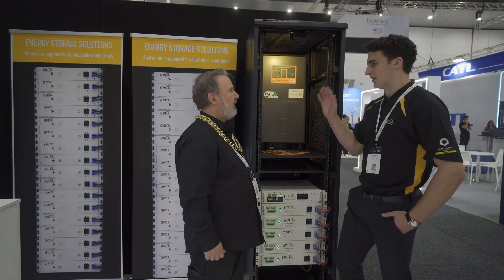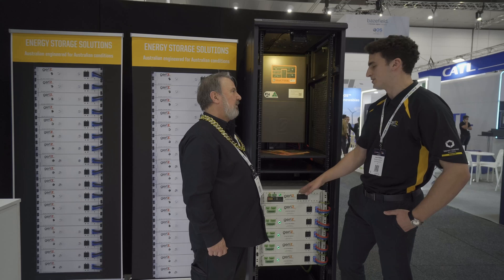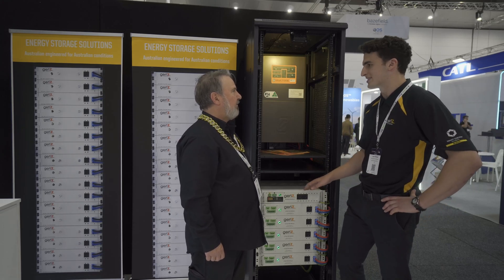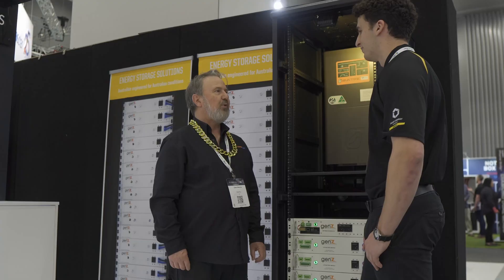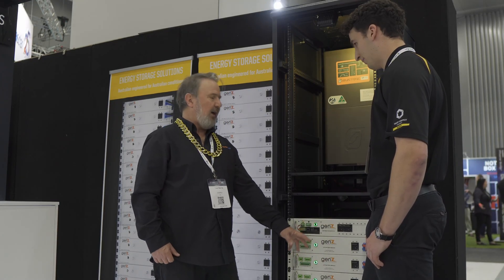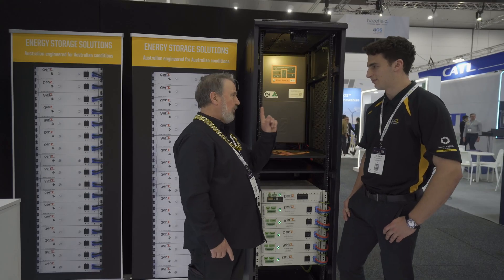This blank is basically for when you've filled up a rack and you want the full 250 amp output. You can then set up two sets of breakers in parallel, which gives you proper management of your fault currents and allows you to have the proper output for the rack itself. The breakers on the front are protection, but if you want to isolate the whole battery system, you can isolate it from here — a single point of isolation, the final point of demarcation.